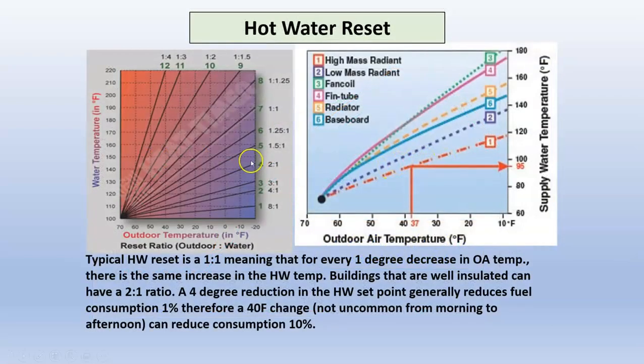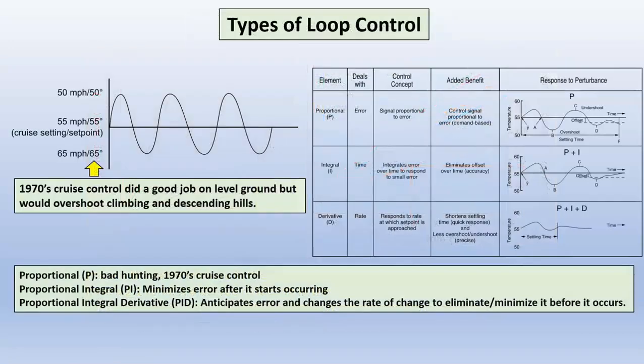Same thing with the hot water. You can reset it from 180 all the way down. Well, if it's a condensing hot water heater, you can get really cold. But for a non-condensing, you can get down to 140 or so. And this saves natural gas or whatever fuel you're using to heat it with.